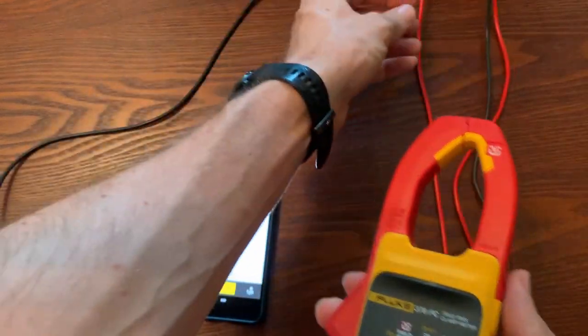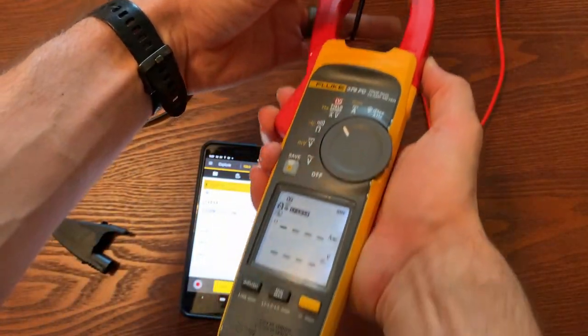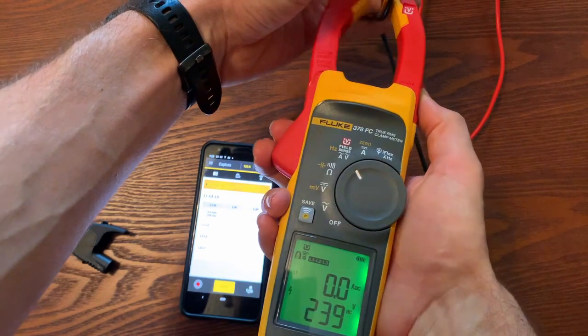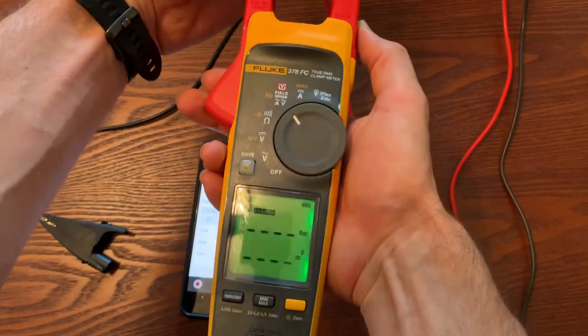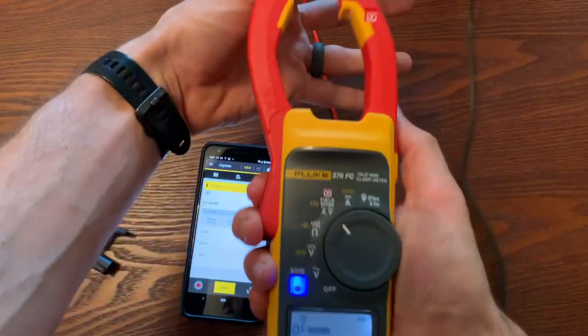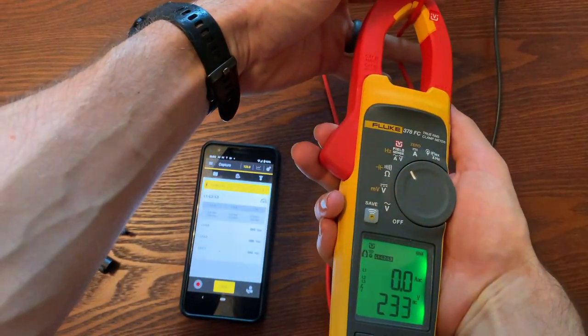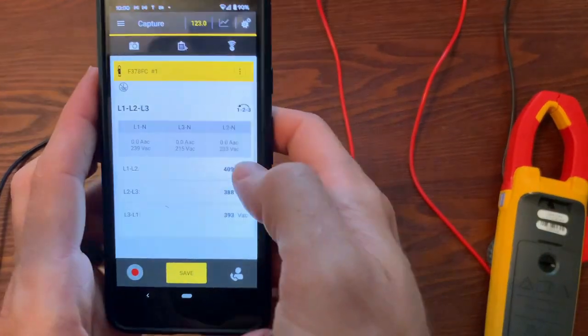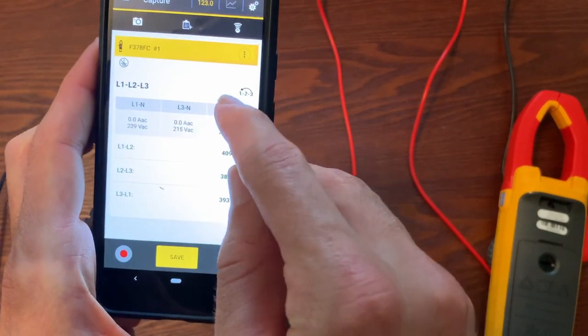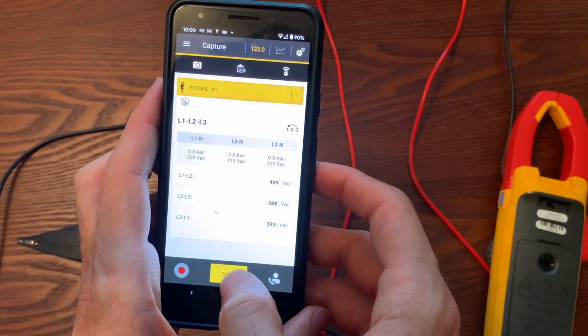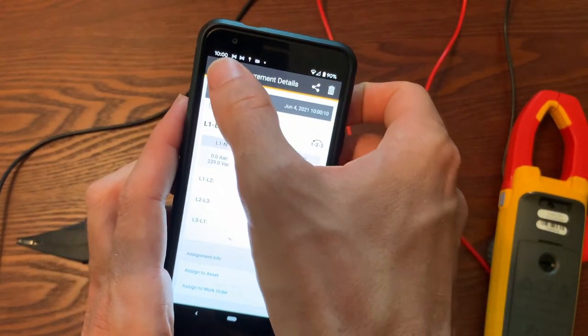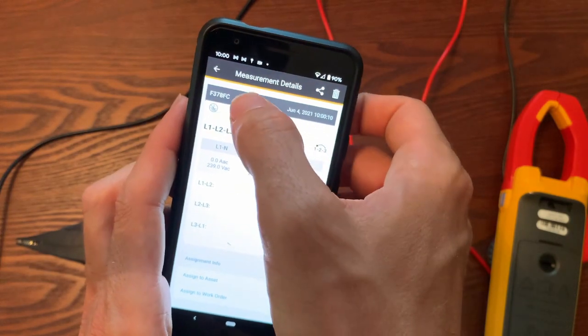Note that all of these connections are being made and measurements are being made without clamping on to an energized circuit. The only wire that's connected to the clamp meter is my common lead and that is connected to earth ground, not to an energized circuit. So if you do need in your facility to take measurements without connecting to energized circuits, this meter will allow you to do that.